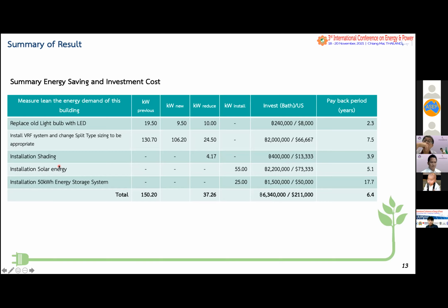And the solar energy that we installed and the energy storage that we installed. For the solar, the cost of investment is about $73,000, and the payback period is 5.1. And for the energy storage, the cost is $50,000, and the payback period is 17.7.